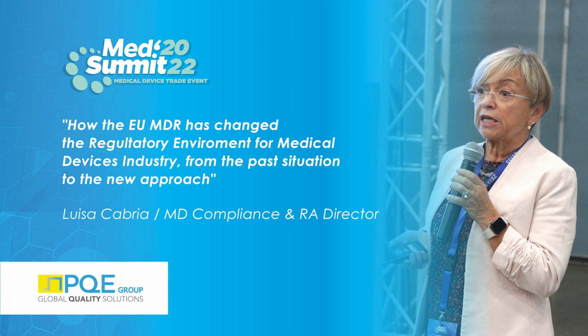There are stricter requirements for economic operators. I will tell you in a few seconds what it means, who is an economic operator. There are specific requirements for manufacturer and device registration within the European Union. The implementation of a unique device identification system called UDI, very similar to the one that is already in force for the United States. The reclassification of devices. We have new rules for the classification of devices, based on risk.